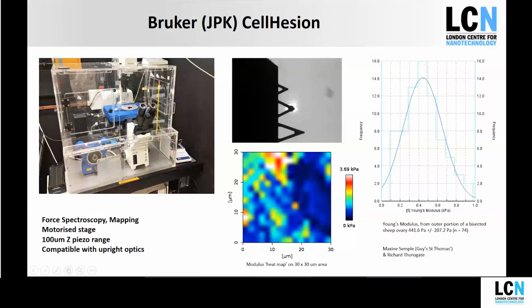So last AFM, we've got two of these Bruker CellHesion systems. This one has a long Z piezo, so 100 microns, but no XY piezo, so it can't be used for cell imaging. So it's useful for cell-to-cell and cell-to-substrate interactions, and investigating cellular mechanics. This is actually on the confocal microscope at the moment, but in theory this stage can be put on any standard inverted microscope or upright optics.